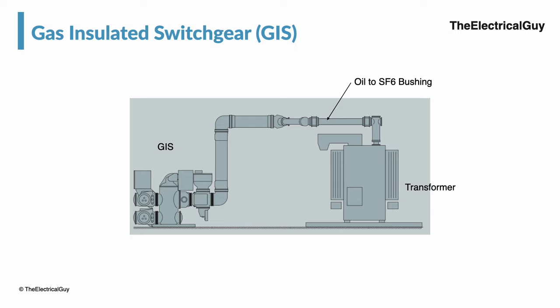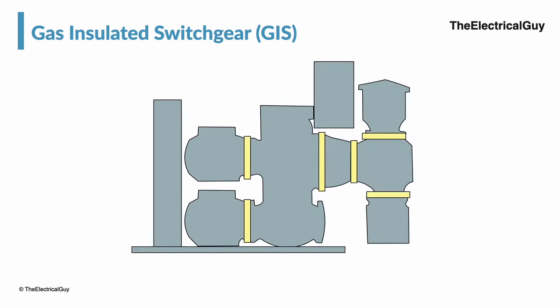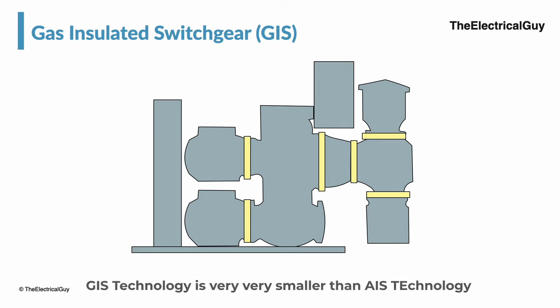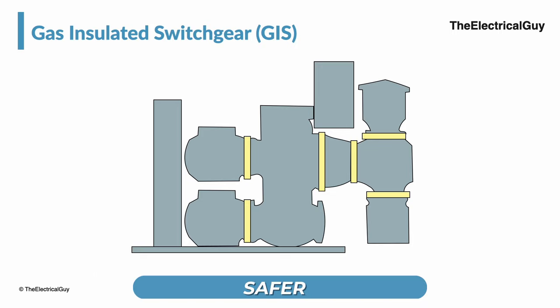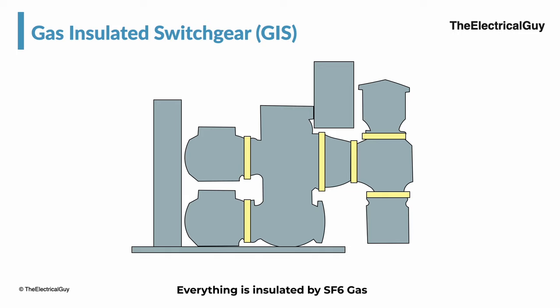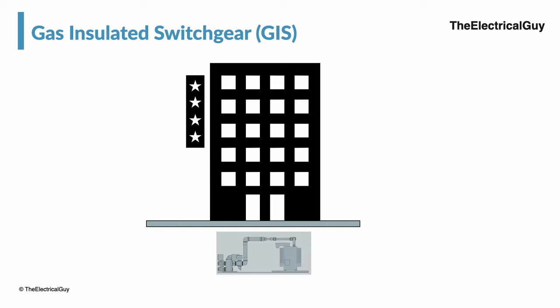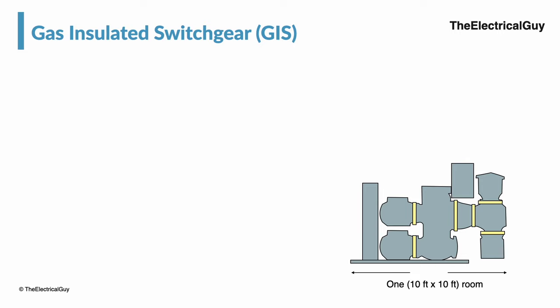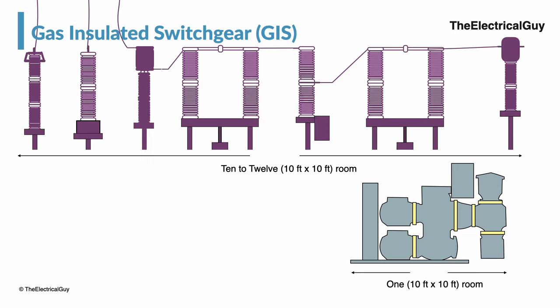Since the dielectric properties of SF6 gas are far better than air, GIS technology is very much smaller in size compared to AIS technology. This technology is also safer compared to AIS since everything is insulated by SF6 gas, and hence GIS is installed even at the basement of buildings. For comparison, one bay of 145 kV GIS can fit into one 10 by 10 room, whereas for one bay of 145 kV AIS we would need around 10 to 12 such rooms.